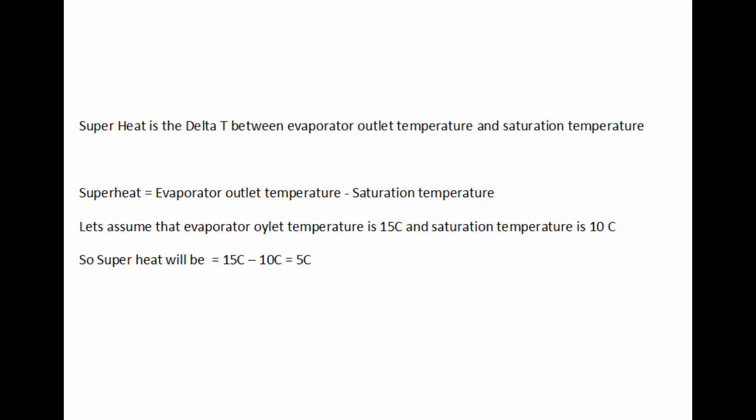Superheat equals evaporator outlet temperature minus saturation temperature. Let's assume that evaporator outlet temperature is 15°C and saturation temperature is 10°C. So superheat will equal 15°C minus 10°C, which equals 5°C.